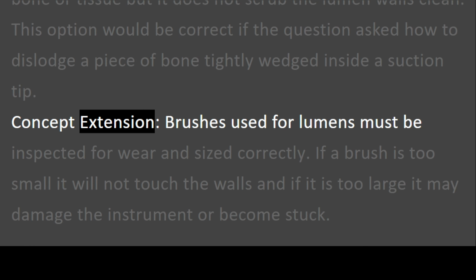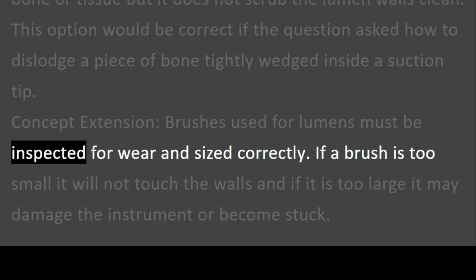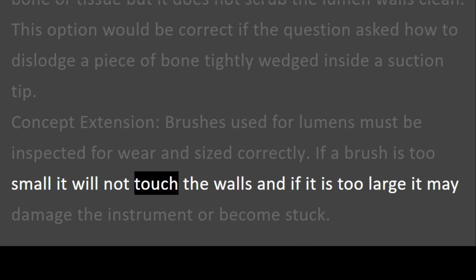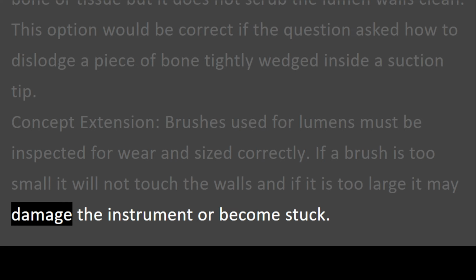Concept extension. Brushes used for lumens must be inspected for wear and sized correctly. If a brush is too small, it will not touch the walls, and if it is too large, it may damage the instrument or become stuck.